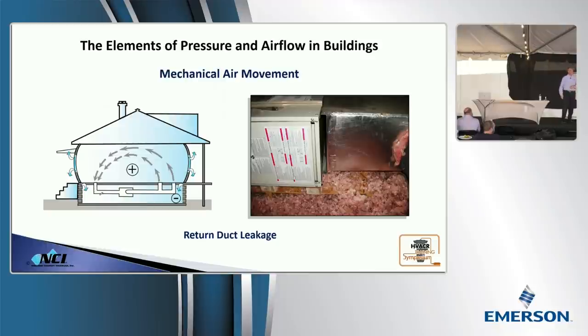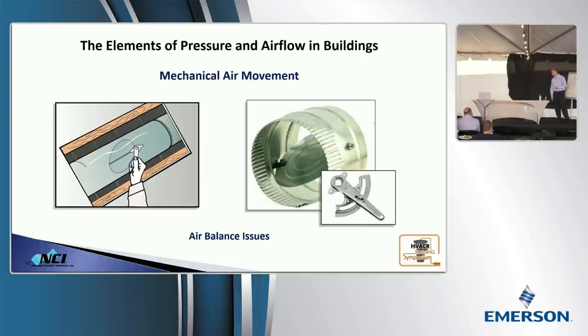Sometimes it's something simple. Other times you've got to dig a little bit deeper. Sometimes it gets into issues where you have to take additional measurements that we may not have on a service truck, when we get into air balancing issues. This is where we have either too much or not enough air being delivered into a space. So as we start to deal with air balancing issues, you have to measure at the registers and at the grills to be able to define if these situations are going on.